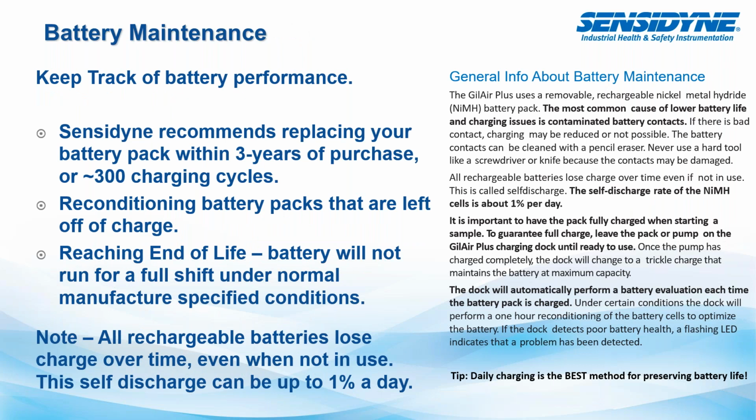Which leads me to talk about some battery maintenance issues. It's important to keep track of battery performance. Sensidyne recommends replacing your battery pack within 3 years of purchase, or approximately 300 charging cycles.